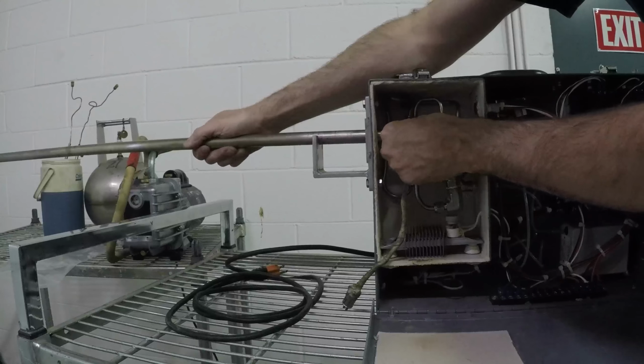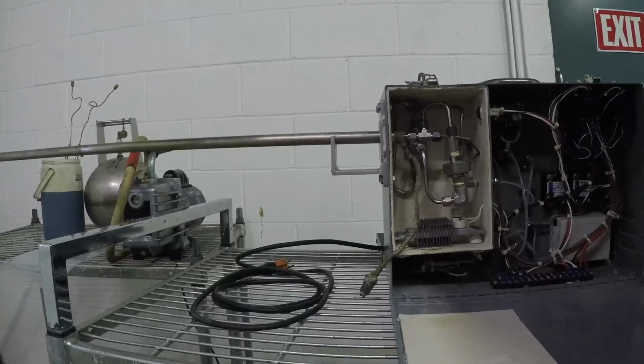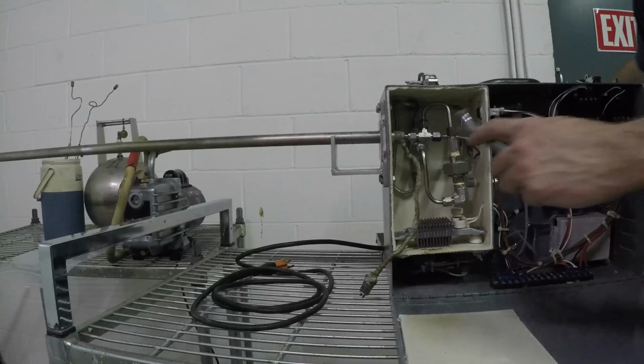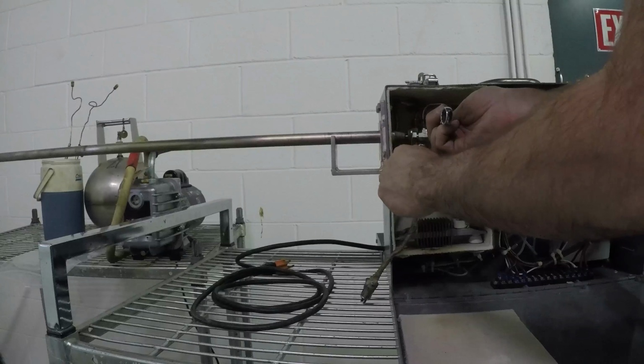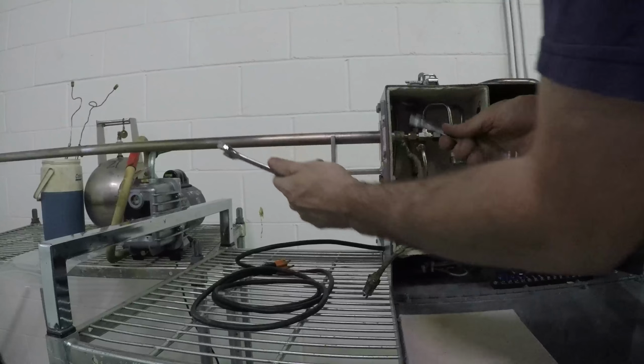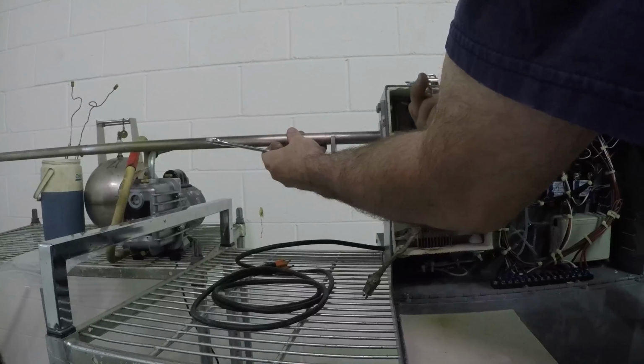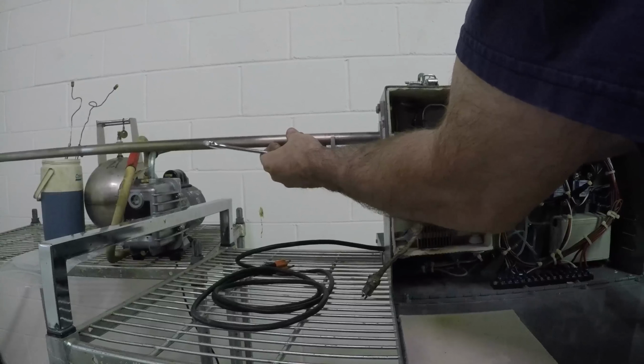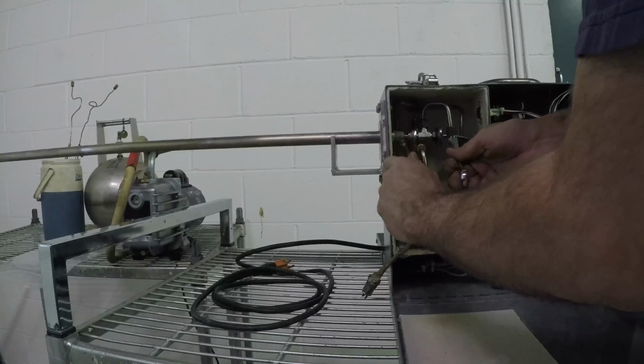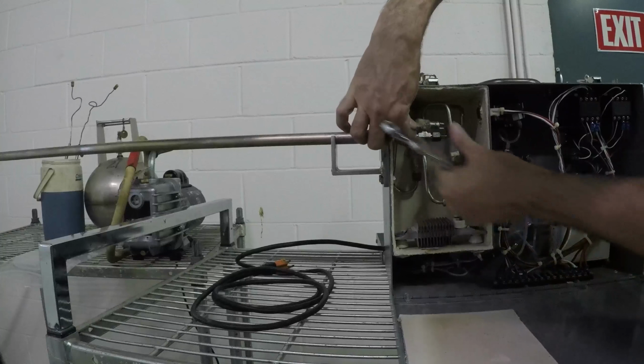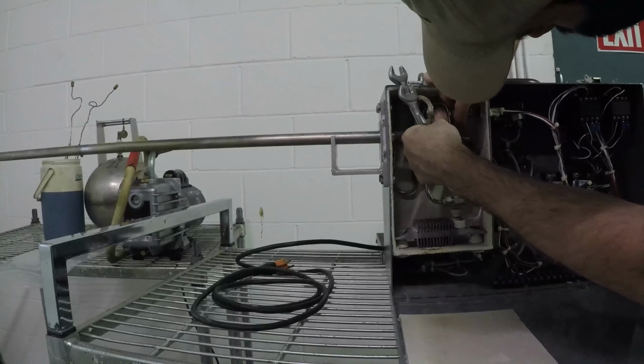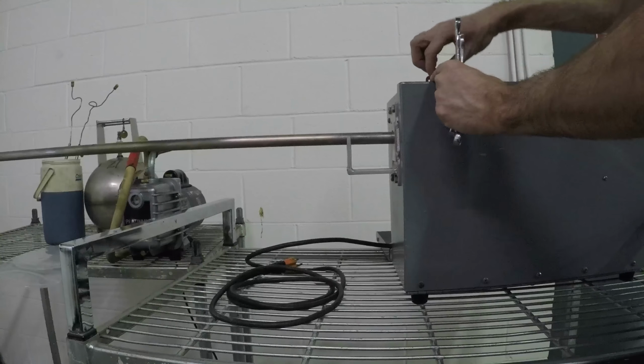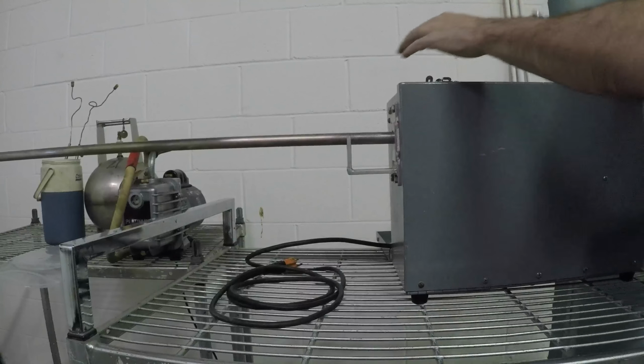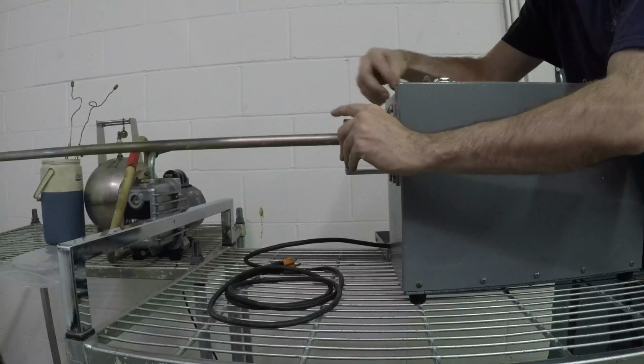Do not force it. If you force it, you'll wind up stripping the threads or cross-threading it, in which case it will never leak check and it will never work again. And we have to replace the whole assembly. With all Swagelok fittings, quarter turn past finger tight is all you need. You just want it snug. And then you plug in probe power up the back. And you reassemble.